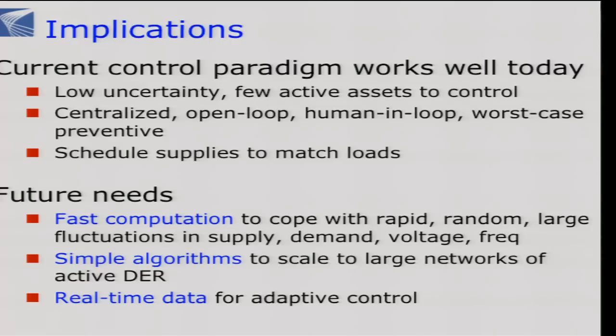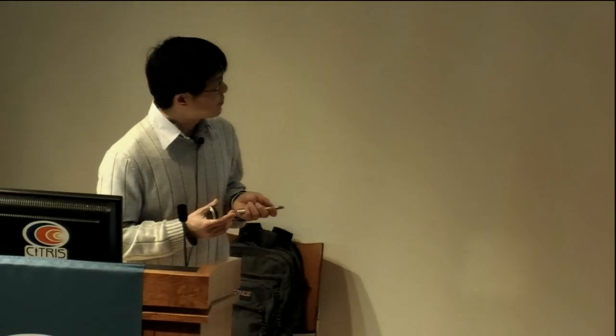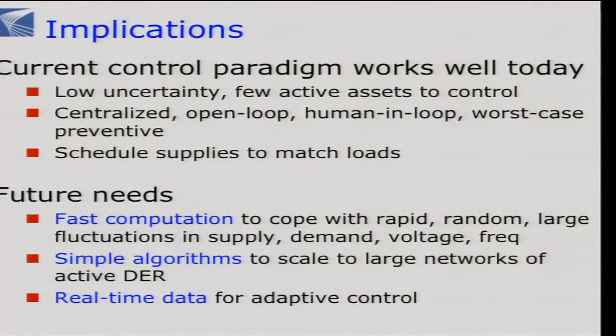The current control paradigm is mainly centralized, open loop, very much human-in-the-loop as you look at ISOs, and worst-case preventive. This works fine because we don't have a lot of uncertainty and have few active assets — say 9,000 generators. But in the future, when we have a lot of DERs — electric vehicles, wind turbines, solar panels, smart appliances, demand response loads — we could have hundreds of millions of endpoints that are active. They're not just passive loads, but active endpoints that can generate, measure, communicate, compute, and actuate.